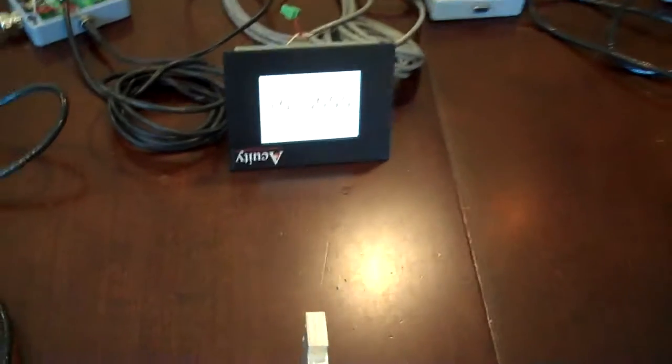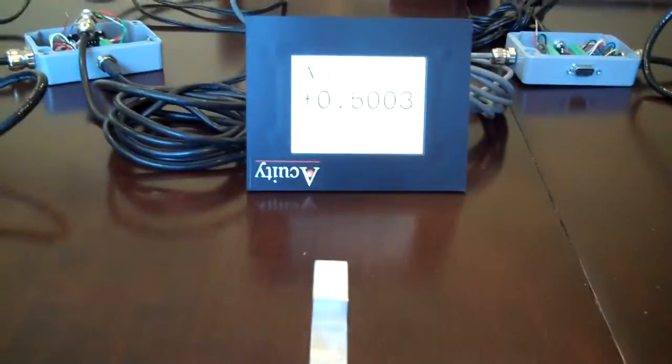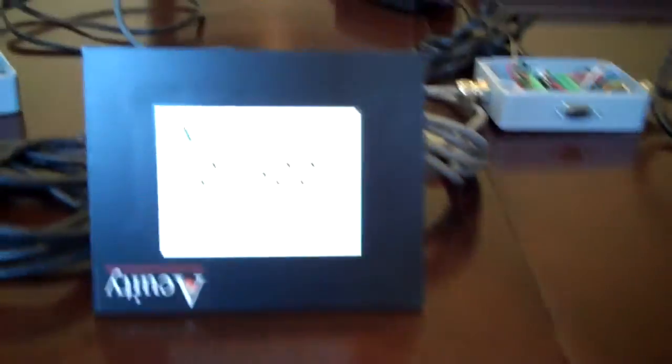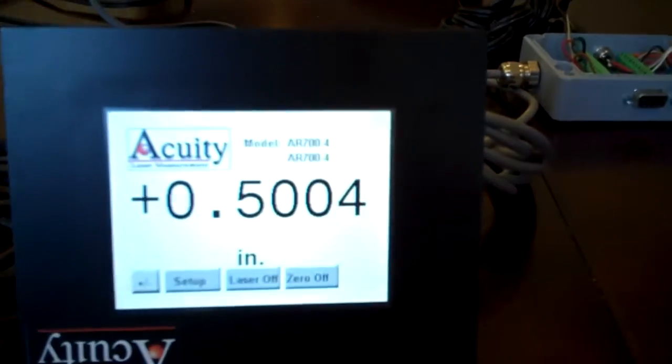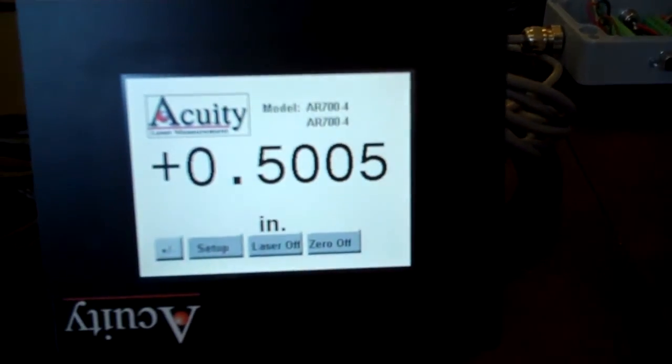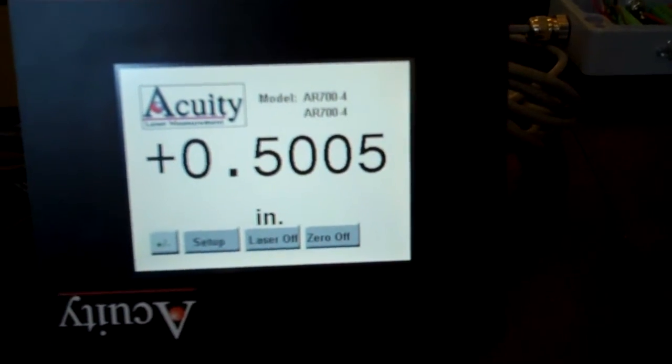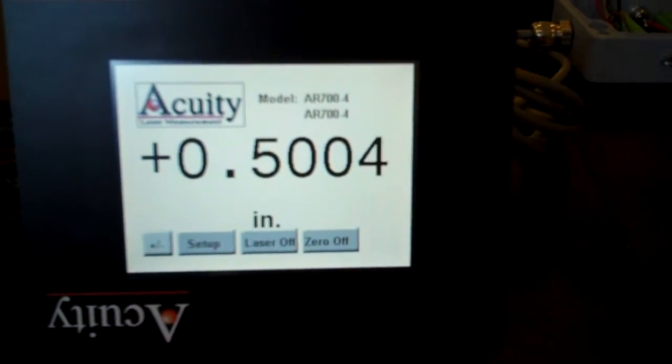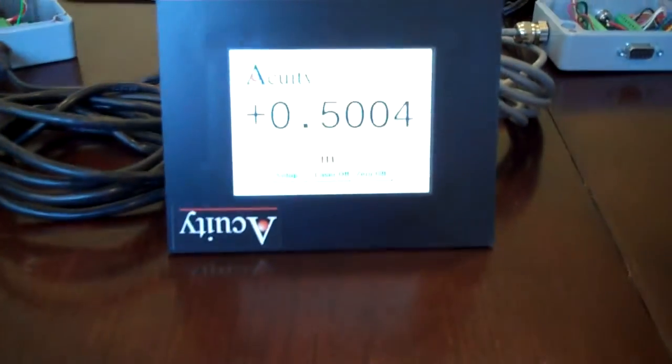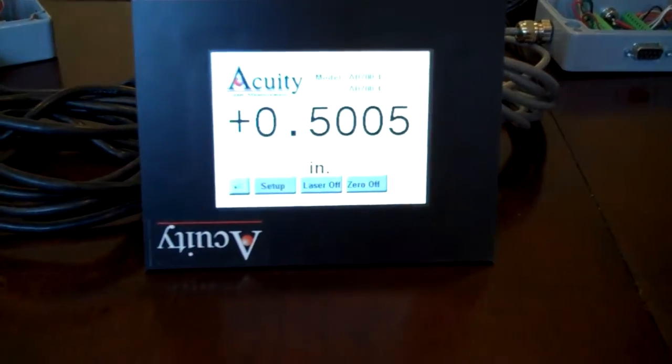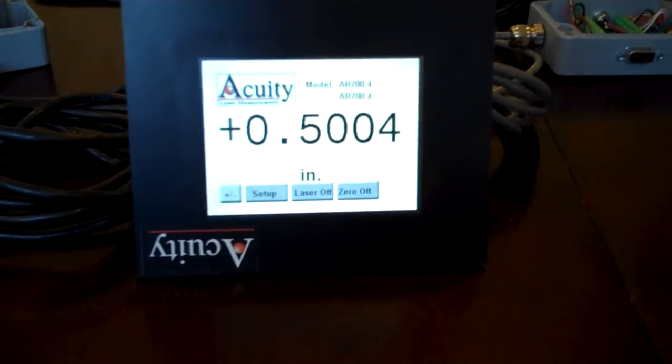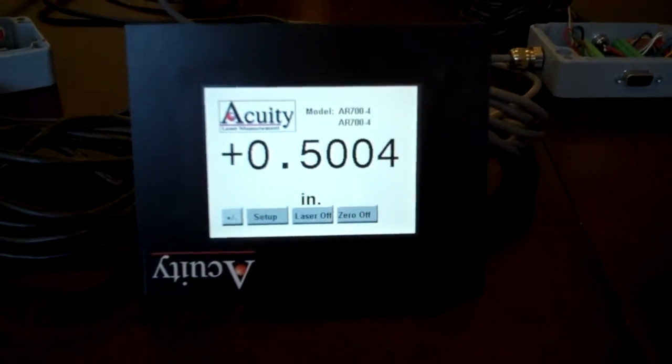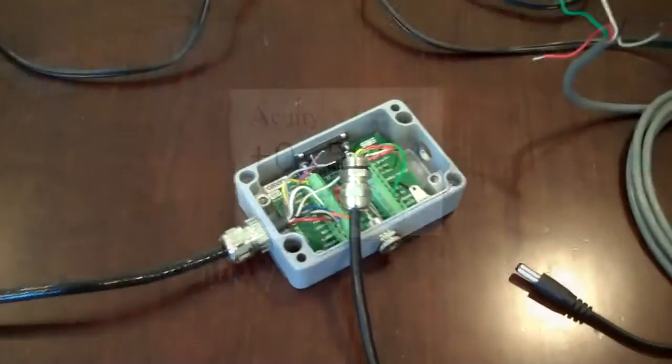This is the setup for a dual laser thickness measurement using the touch panel display and two Acuity AR700-4 sensors. Right now it is properly set up and it's measuring the thickness of a part which is approximately a half inch thick. And that is correct because this is a half inch part right here. In this video I will show you how to set this configuration up.